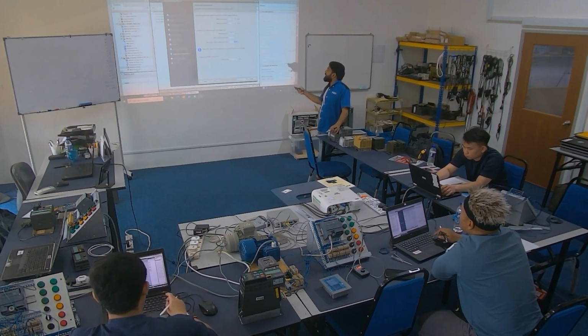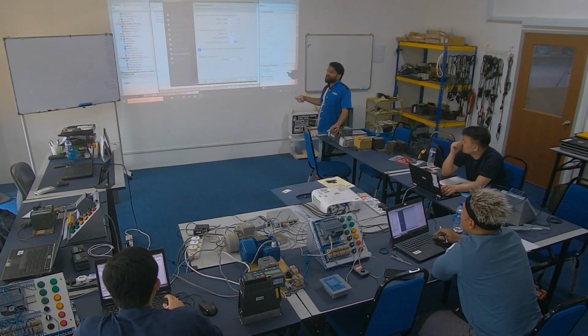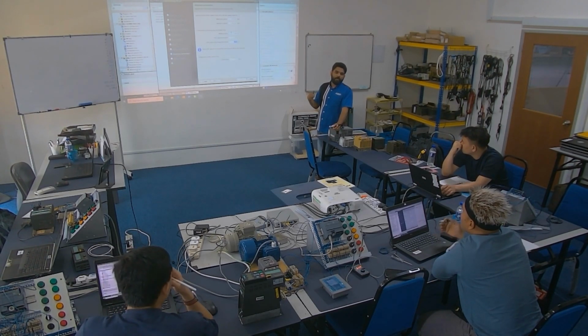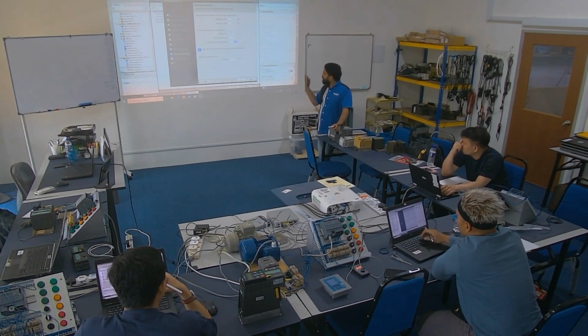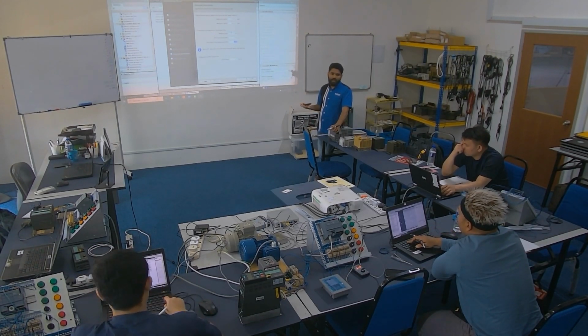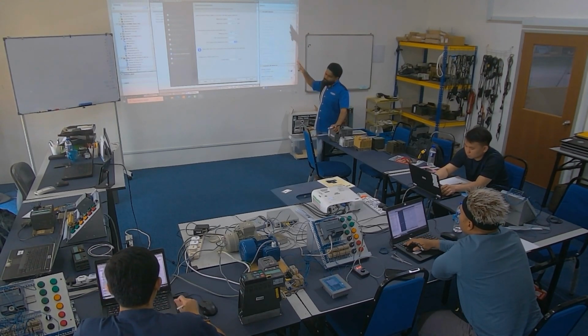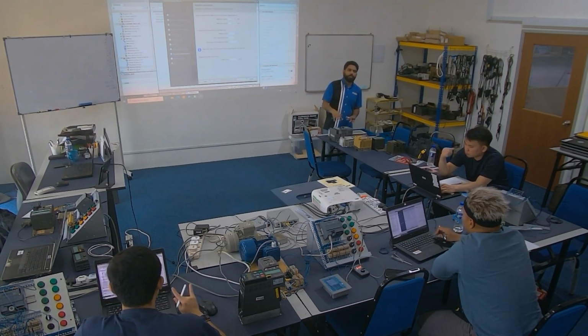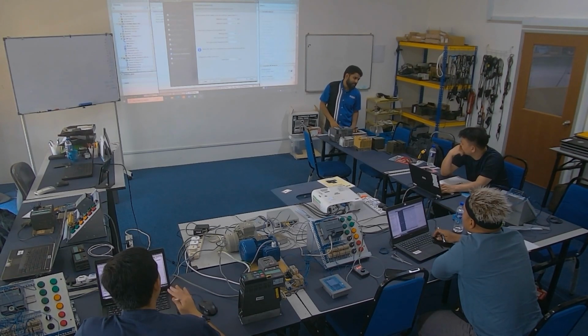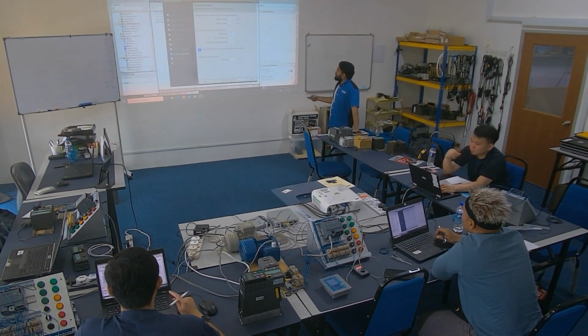This one is off quickly, means suddenly got error, trip, communication loss, suddenly off. So this one also you can use 1 second or 0 second also can, no problem. But now can lah, because this motor is not connected to any machine. Let's put the same, 1 second. Okay, next.